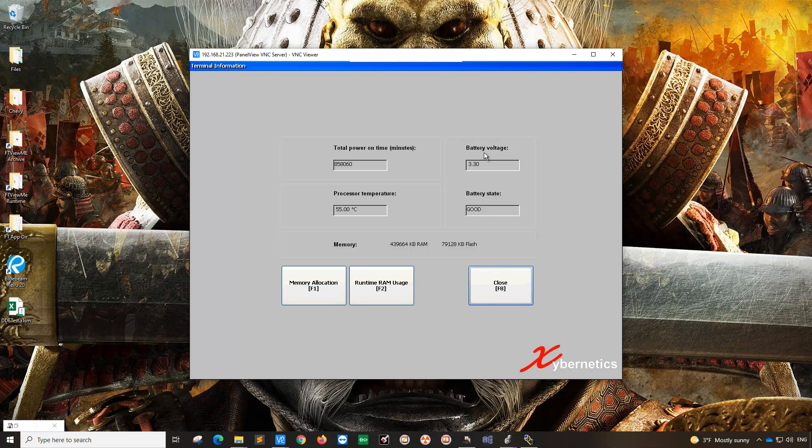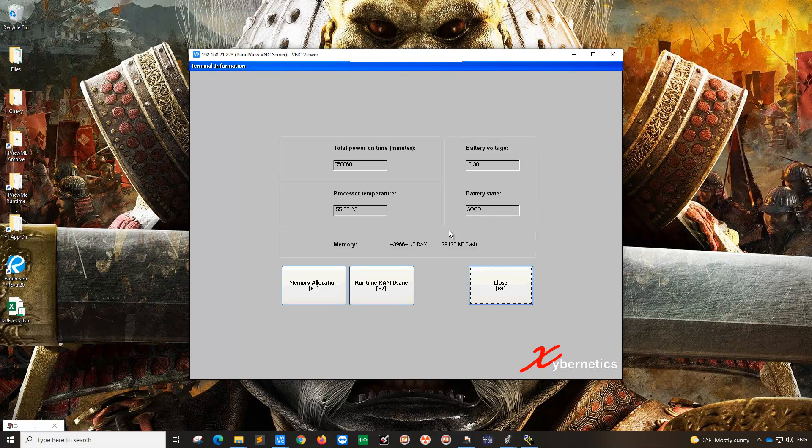I've sometimes seen in some of the older sites the battery voltage is 2.95, which is still good. I'm not too sure what the minimum value is. In some of the Allen Bradley PLCs, they have recommended 1.8 volts. But again, I would recommend you read the manual to find out what's the latest.